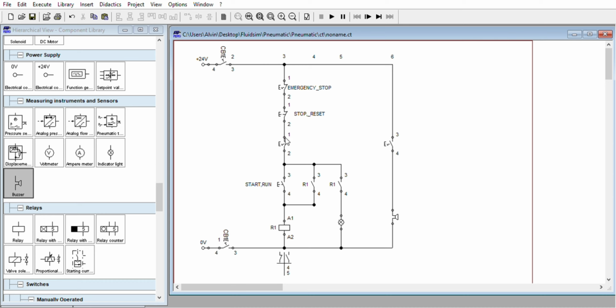reset, TOR, thermal overload relay, and this one is not connected here, because otherwise it will defeat the purpose of the signal. So this will turn off, so no more supply here. So the supply is here, going to the buzzer. So you don't have to cut off the supply of the emergency alarm or the tripping alarm if there are troubles or overcurrent in the motor.